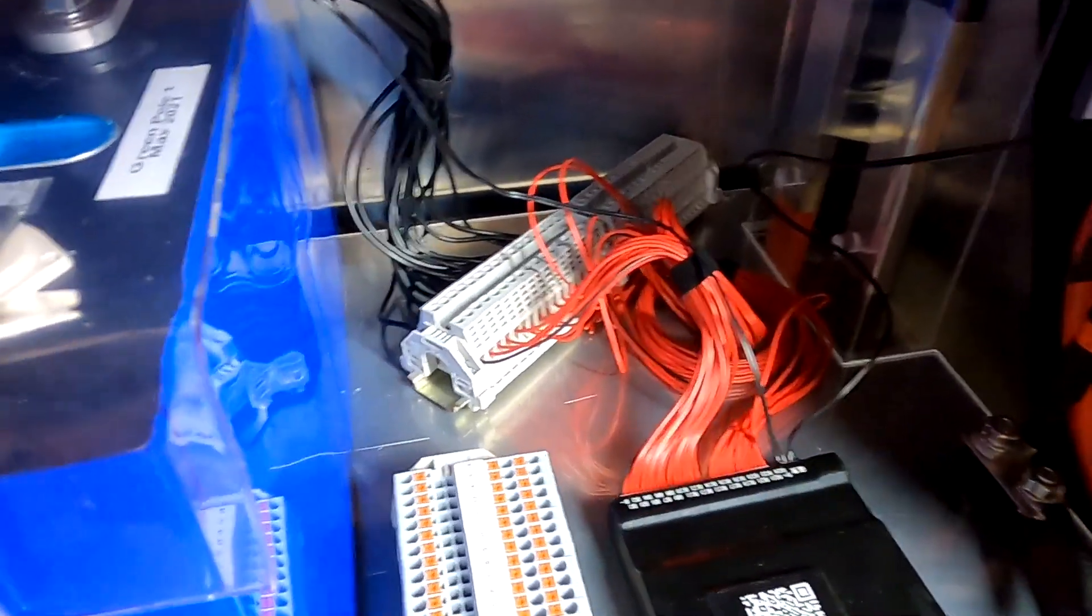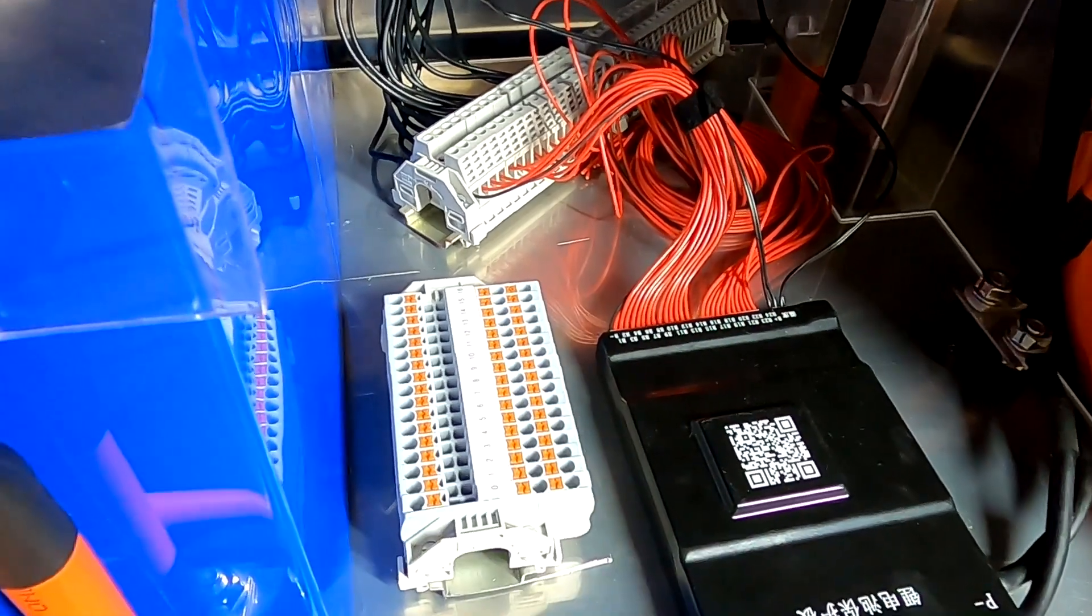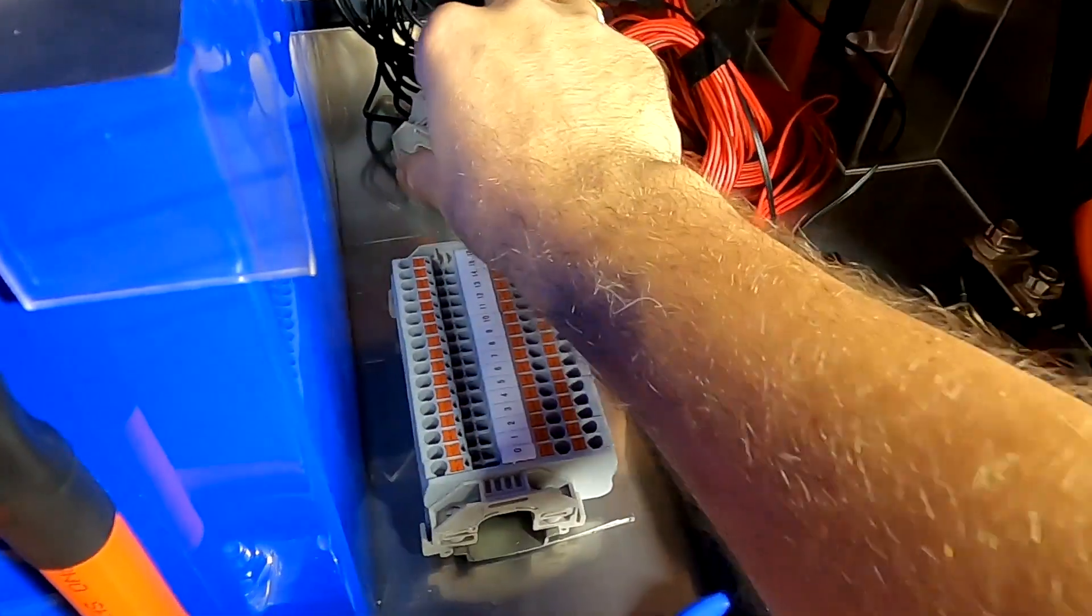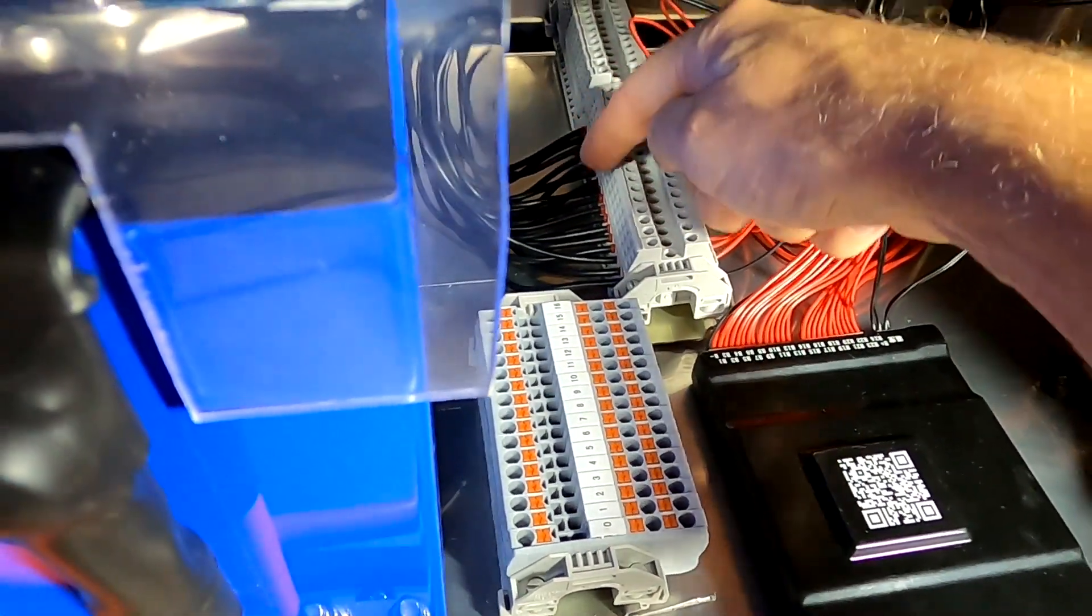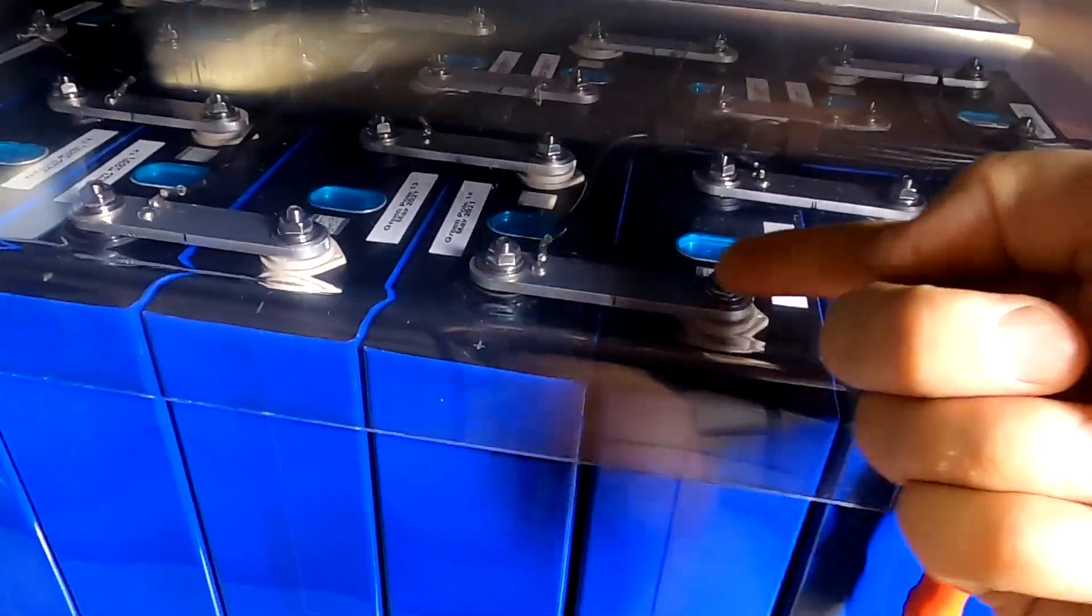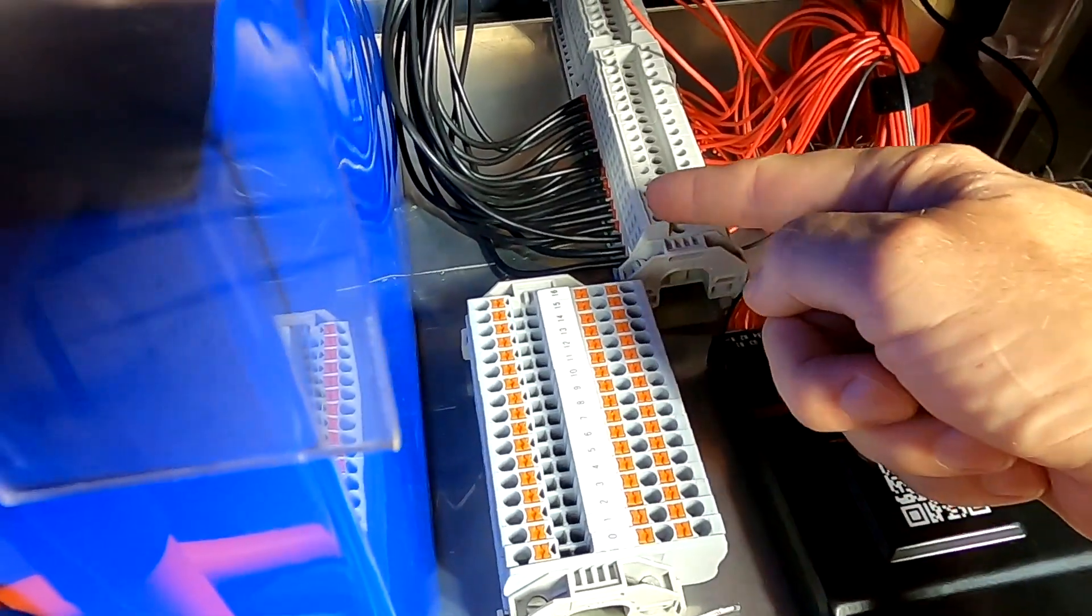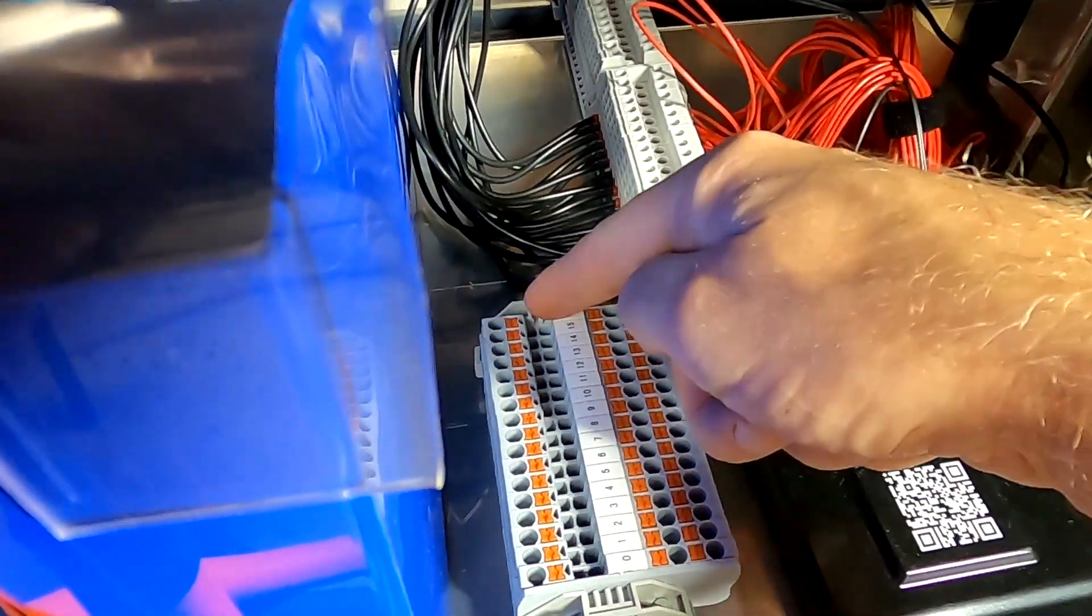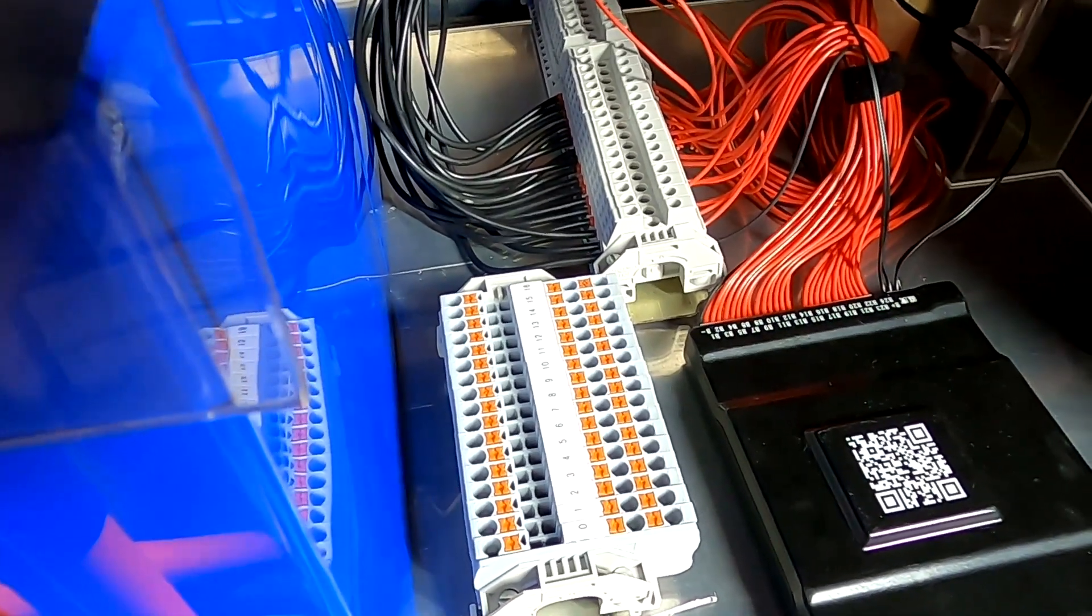Okay, so now here comes the task to transfer our wires from this terminal row to this terminal block here. And we can only do this one after another because I cannot undo all these screws here and take off all these cables here, because if they touch, it will be a short between two cells. Whatever touches, it will be short and it will blow our five amp fuse. So I have to start with the negative terminal, number zero, and then first cell up to sixteen, all across here. And we just have to push them in, so there are no screw connections or something. It should go fairly quickly.